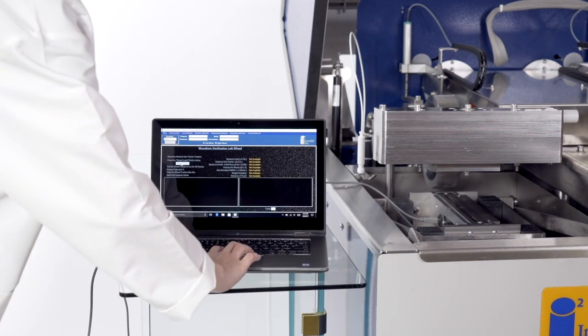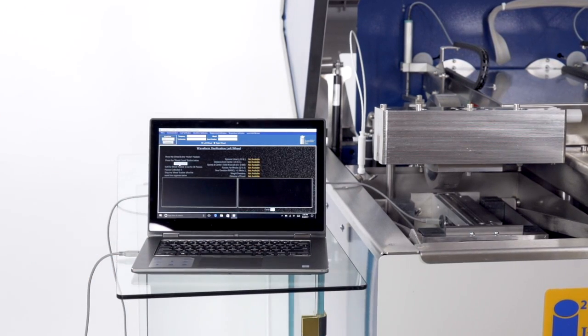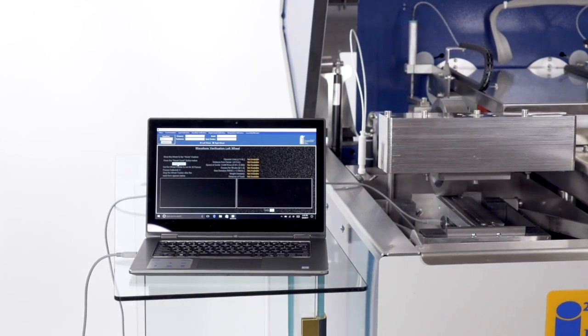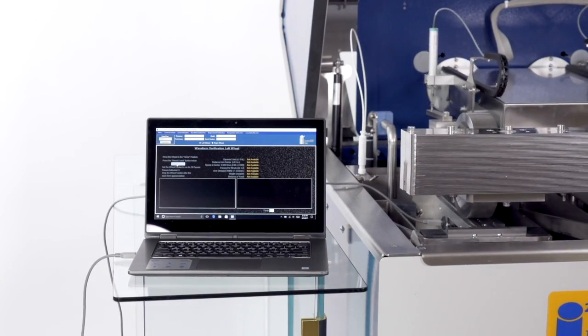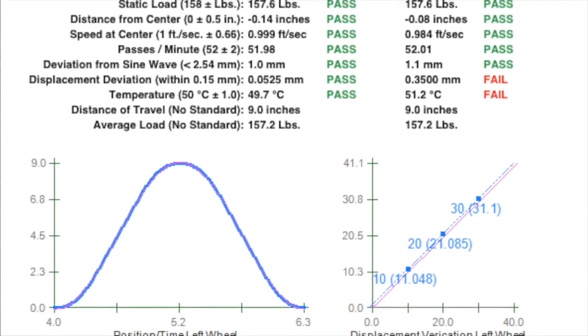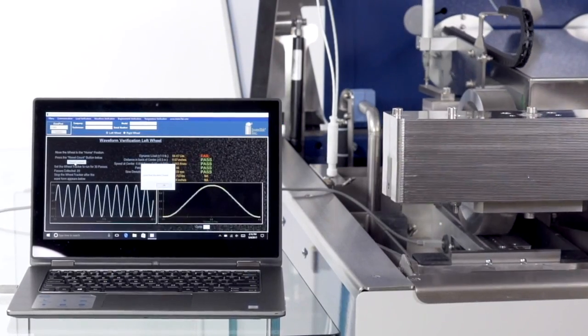The HWT Pro spec software brings it all together with an easy-to-use data input screen and step-by-step instructions to gather all verification data. The software generates a verification report with a pass-fail summary of calibration parameters and a graphical comparison of the wheel to the sinusoid waveform.